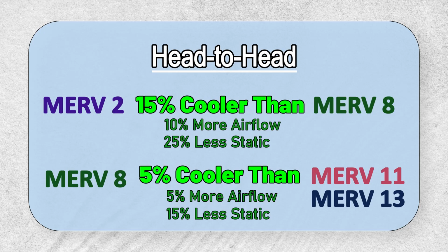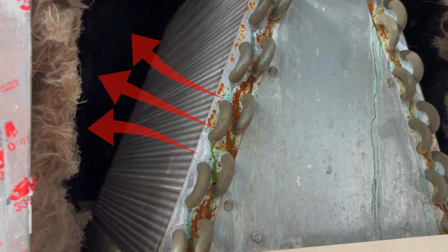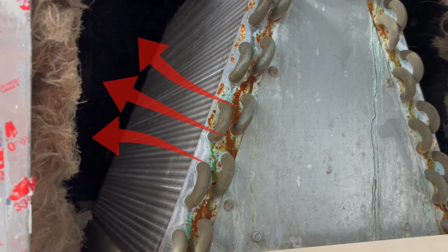Ultimately, the airflow characteristics that we saw with the MERV 2 were the ideal ones that prevented us from tripping that limit switch like we did with the pleated. And even beyond the heating cycle, a similar issue can still occur during cooling cycles. You can essentially not have enough of the warm air circulating over the coil, the coils freeze up, you get a block of ice, and then you're really restricting airflow and really hindering performance. So it really isn't just a heating issue, it can also be a cooling issue by restricting airflow too much.